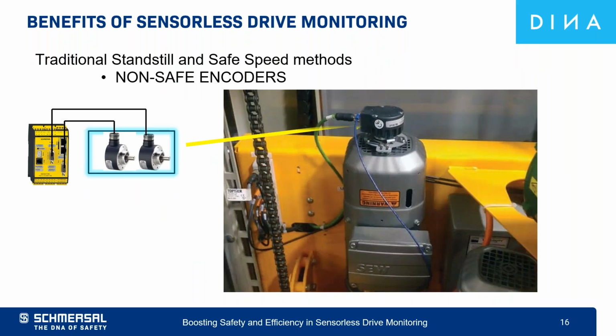Many existing motor applications already have motors or encoders on them. So you ask, why could I not use this information from those encoders? Well, you can. The information that's already being used by these encoders can be shared via encoder splitter modules, but they're costly. They take up a large footprint inside a panel, and not to mention the fact that they're not safety rated either. So you'd still require, in most cases, a second encoder for a safety application.